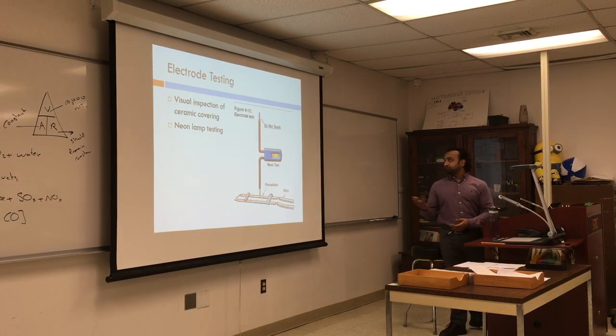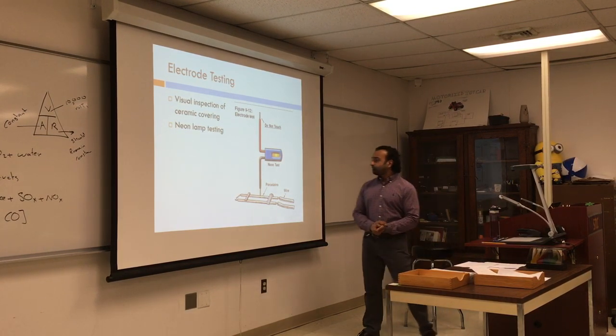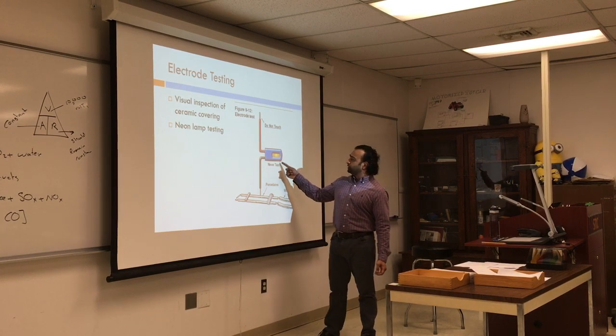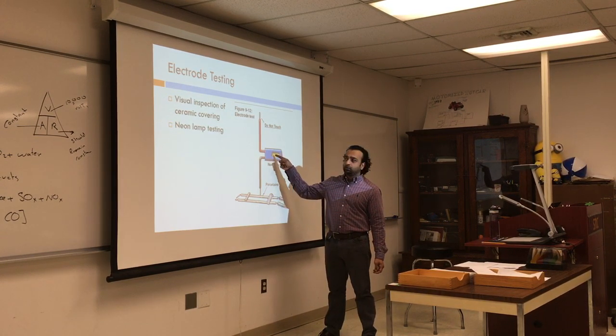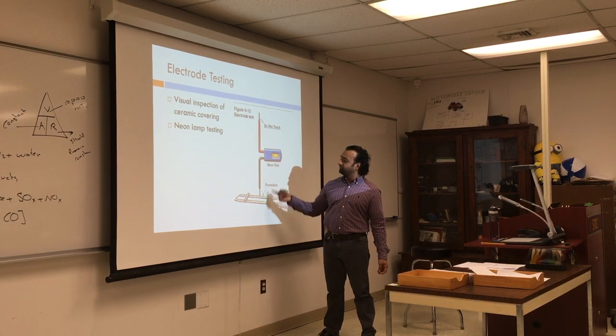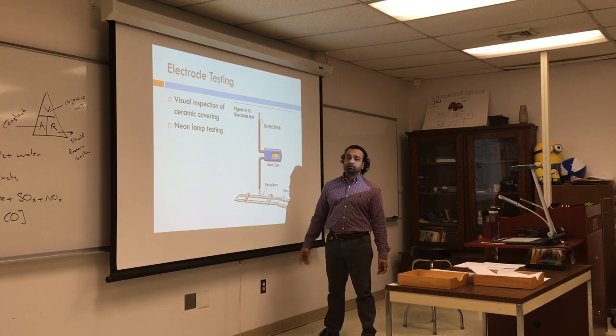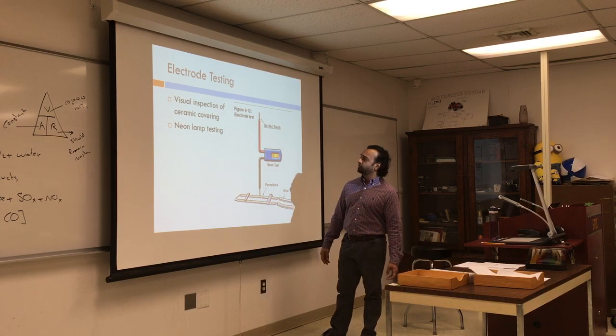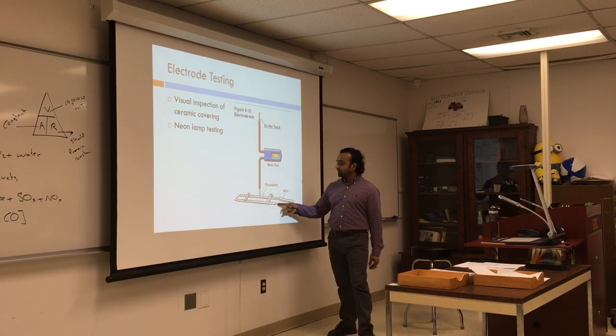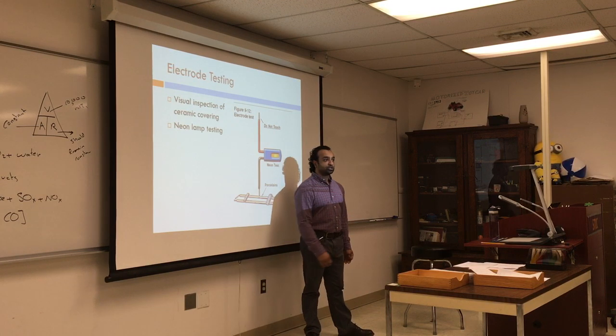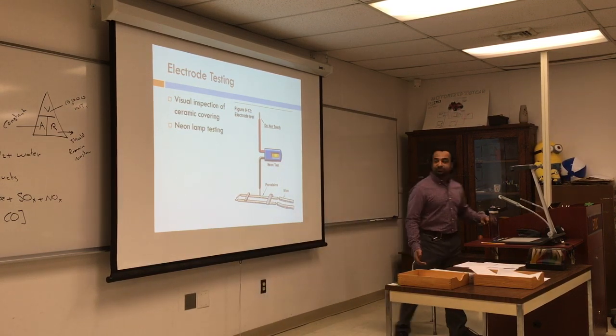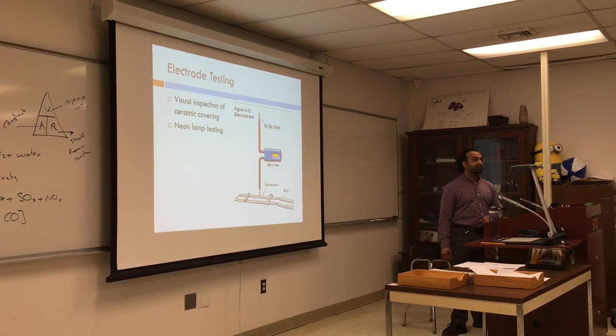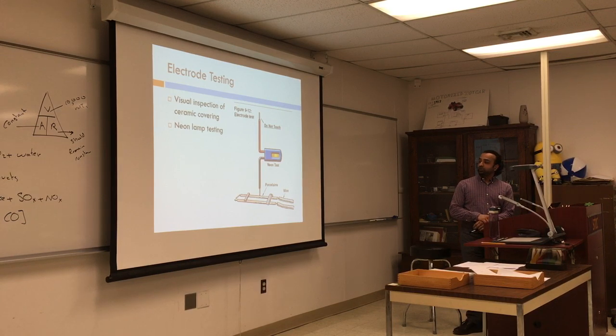There's another tool that I've seen, where you run a small light through it that will take the high voltage and show if there's any crack in it. But that's for when visual inspection is not possible. You can go through the entire porcelain and make sure there are no cracks in it, because sometimes there is a hairline fracture that you cannot see visually. It is a good way to measure that.